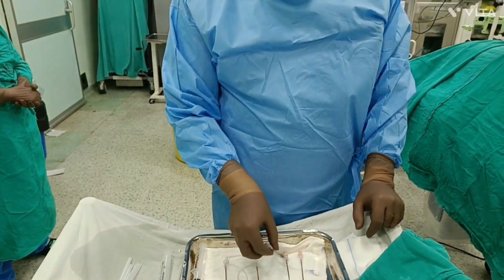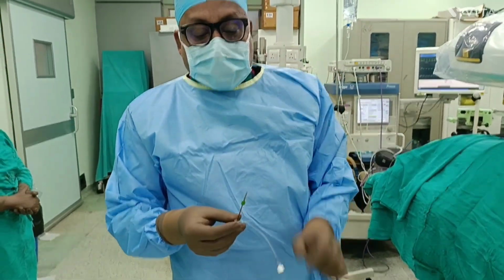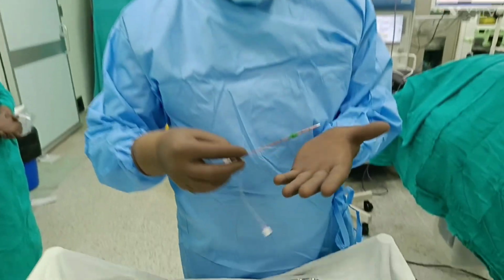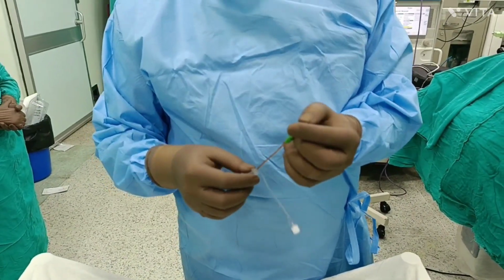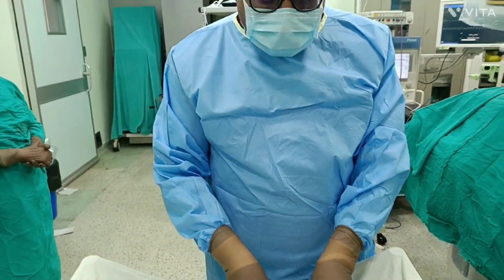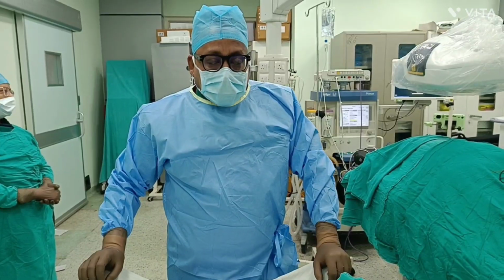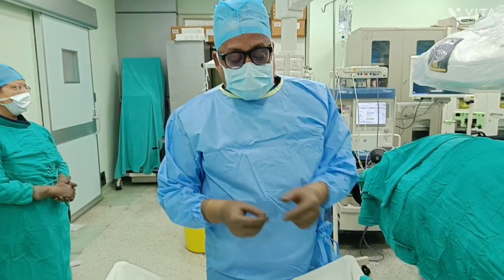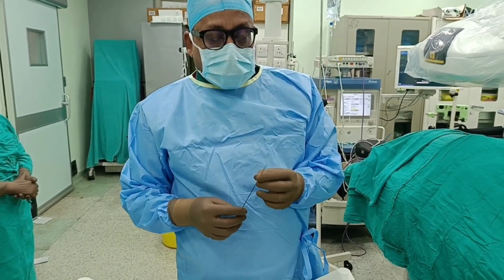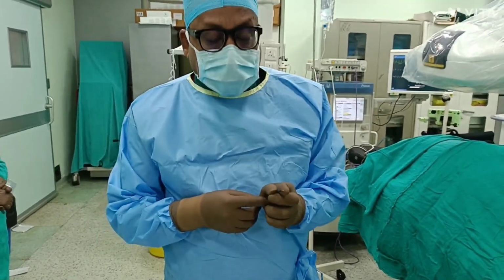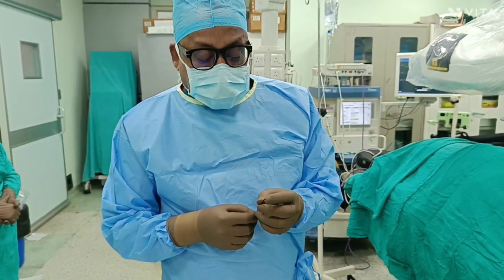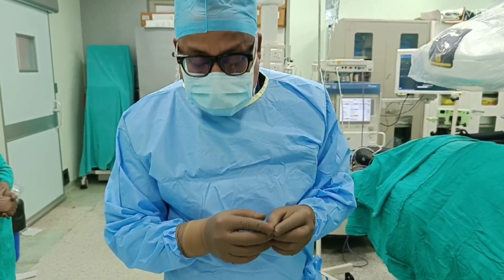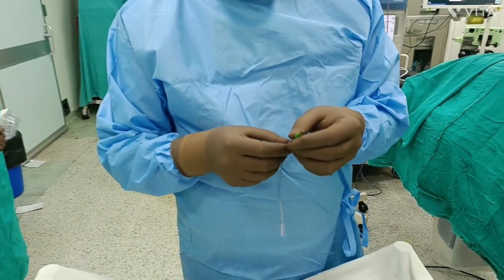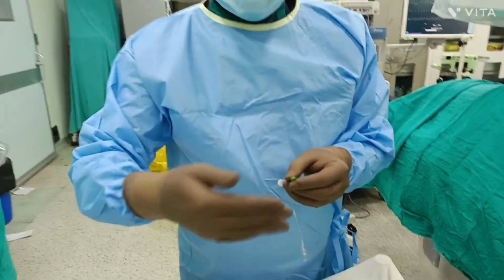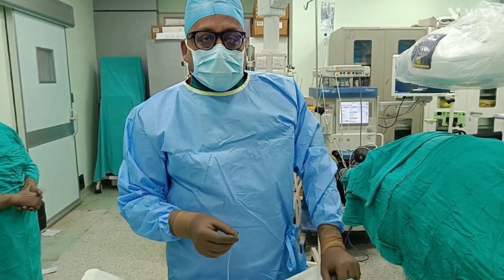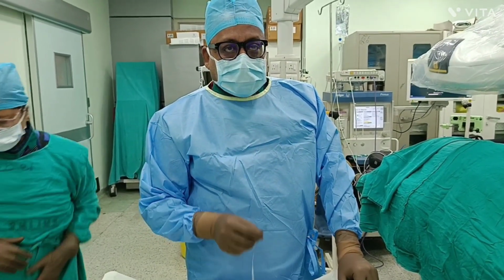But in the cooled radiofrequency, it is important to understand the difference, that we are using this cannula, which is a cooled radiofrequency cannula. It has 17 gauge diameter with a 4 mm active tip. So there is a difference between the placement of these RF cannulas while doing the standard radiofrequency or the cooled radiofrequency. For the standard radiofrequency, we need to put the cannula parallel to the nerve to get it burned mostly. Why? Because the lesion of the standard radiofrequency happens on the side of the active tip. But in the cooled radiofrequency, the lesion is being made at the tip of the cannula. So that makes the difference in the placement while doing the cooled versus the standard.